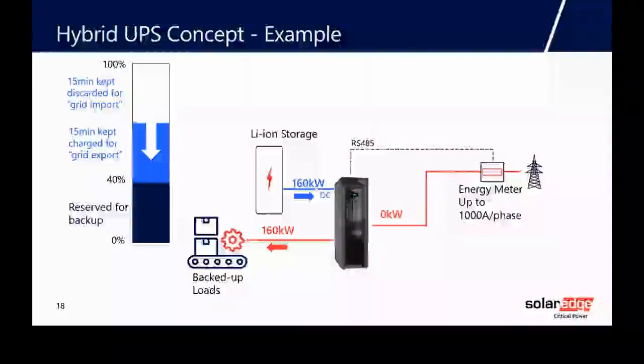Typically people have batteries for say 5, 10, 15 minutes. So they would have a power cut, and if there was still a power cut after 5 minutes, they would do a controlled shutdown. Now we can easily increase the size of that battery to say 1 hour and make it a lithium battery. As mentioned earlier, power is required for 30 minutes at a time. So if we have a 1 hour battery, we can comfortably use 30 minutes of it for grid services, and still have 30 minutes left for critical power.